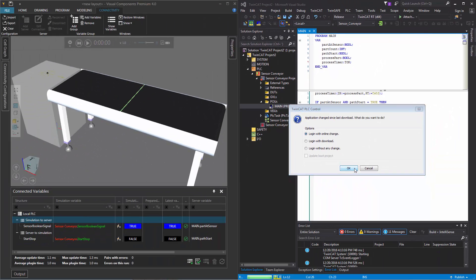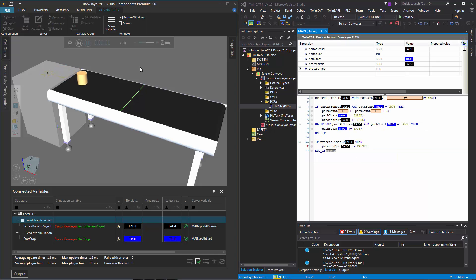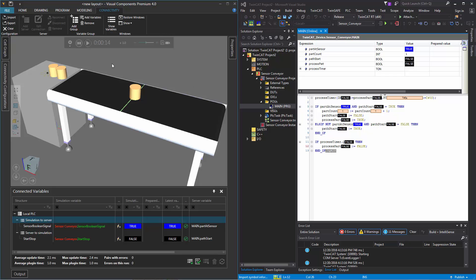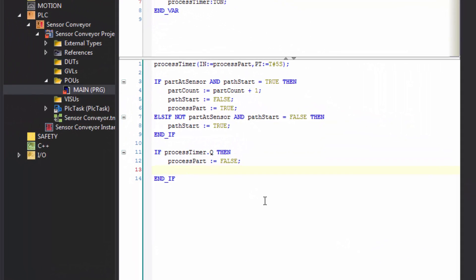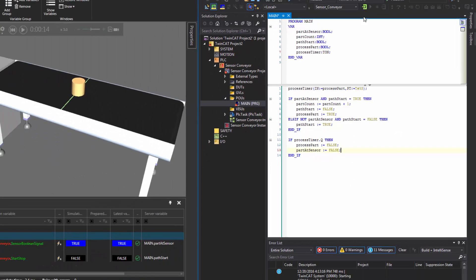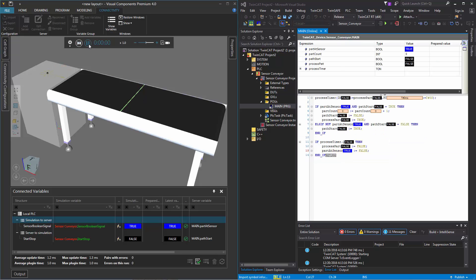The part stops but after five seconds the path did not turn back on. Let's stop and fix this. We actually need to set part_at_sensor := FALSE in the PLC when the timer finishes. So after the timer completes, we add part_at_sensor := FALSE; Log in again with those changes, reset the simulation and run it again. The part stops and then after five seconds the path turns back on.